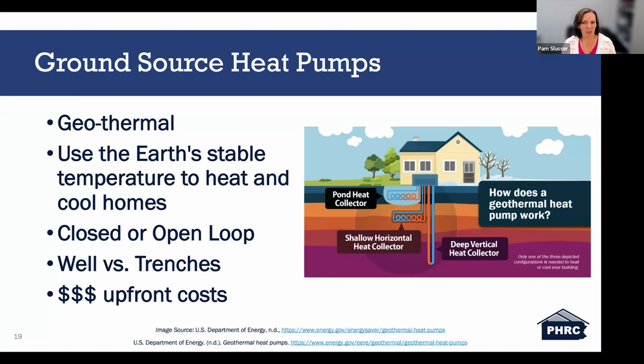The benefits are similar to your closed loop system. It can be a little less expensive than the closed loop, but in some cases, or most cases, more energy is needed to pump water through the system. Also, as I said before, it needs that good water supply and a safe discharge, which can be a challenge at times. You might not be able to get that, especially in our summer months when sometimes it stops raining and it gets dry. And then with the closed loop as well as the open loop, you can have trenches. These are your horizontal loops. So they'll dig down typically 5 to 6 foot.